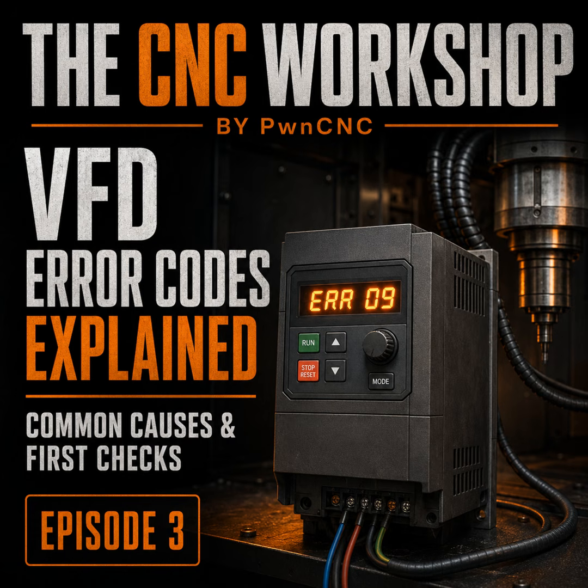So if the spindle stops during a cut, stop the machine. Don't just clear the error and hit resume. Correct. Stop the job, record the exact error, and look at what happened. Before inspecting spindle wiring, disconnect power from the VFD and allow it to discharge according to its manual. And don't open an enclosure or touch electrical terminals unless you're qualified to work around that voltage.